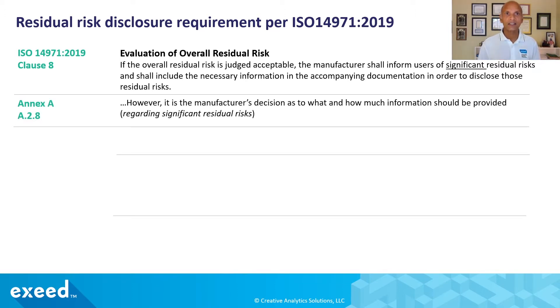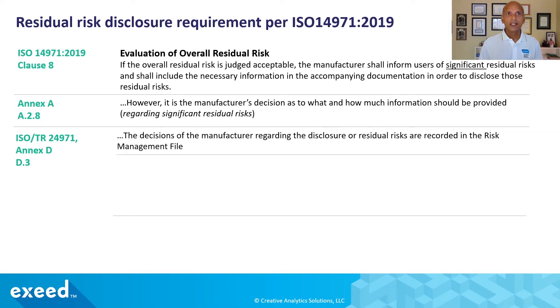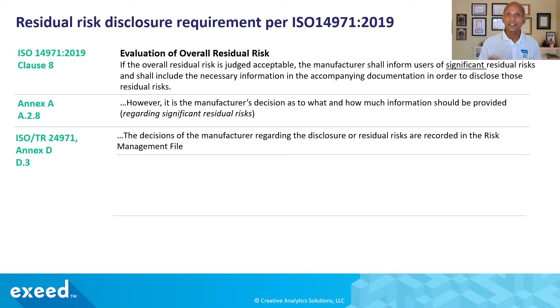In Annex A A.2.8, it is the manufacturer's decision as to what and how much information should be provided regarding these significant residual risks — so it's up to you. Looking at ISO TR 24971, which provides more guidance and clarification, in Annex D D.3, the decisions of the manufacturer regarding the disclosure of residual risks are recorded in the risk management file. So you should document your decisions.